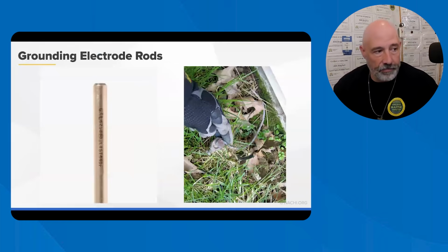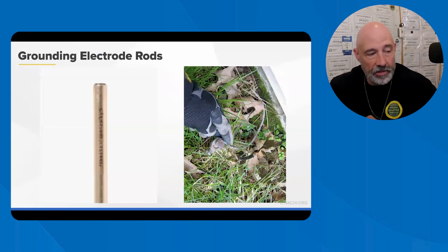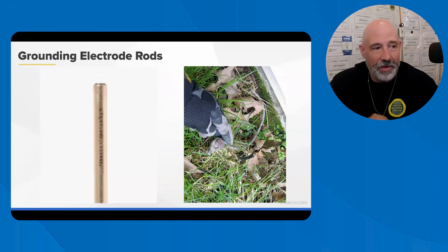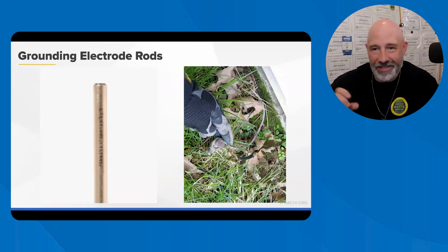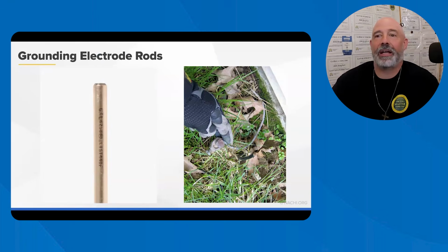So there you go. This is what a grounding rod actually kind of looks like. And pounding on the ground is sometimes a pain. But grounding rods are typically about 5/8 inch diameter. They're made of copper or galvanized steel. Ground rods and pipe electrodes must be at least 8 feet long and in direct contact with the soil. If rocky conditions prevent vertical installation, ground rods may be installed at an angle of 45 degrees or buried in a trench at least 30 inches deep. The top of the rod should be flush with the grade. So that protects it from being damaged.